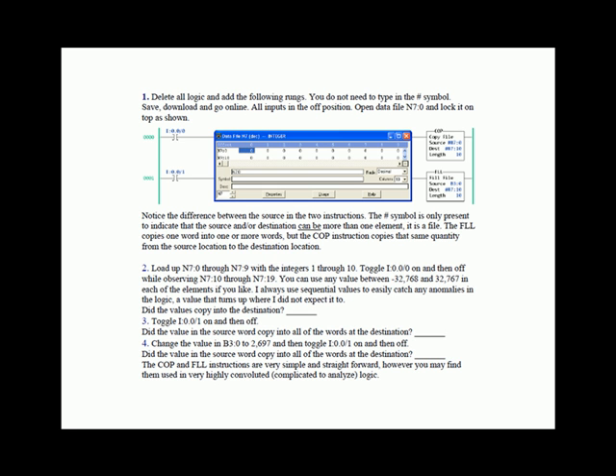Now you could use any integers you want between minus thirty-two thousand seven hundred sixty-eight and as high as thirty-two thousand seven sixty-seven in each of the elements. However, I always use sequential values that somewhat match the memory locations. That allows me to more easily catch any anomalies in the logic. If you use sequential values and an anomaly shows up, it'll be a value that turns up where you don't expect it. But if they're just random numbers, you're unlikely to notice.